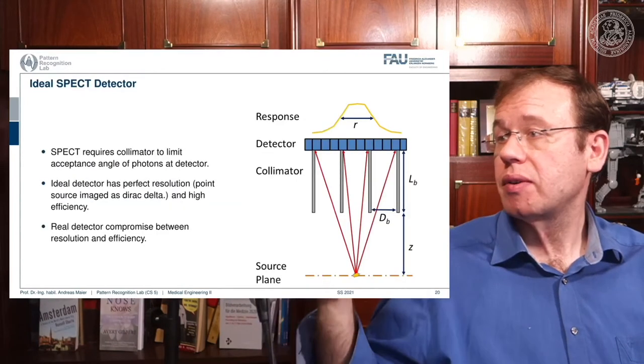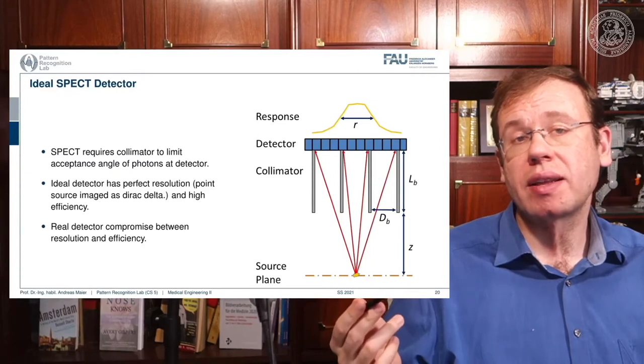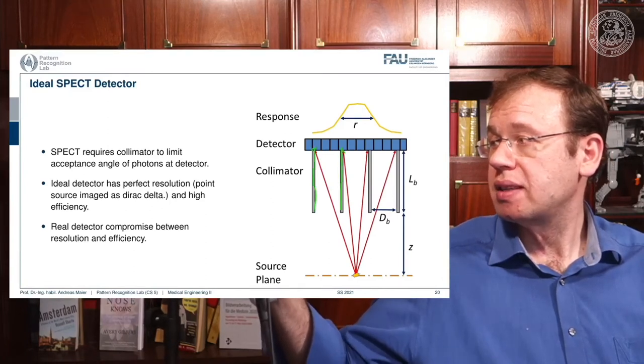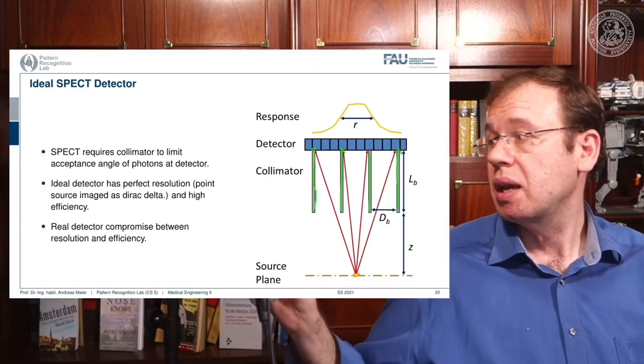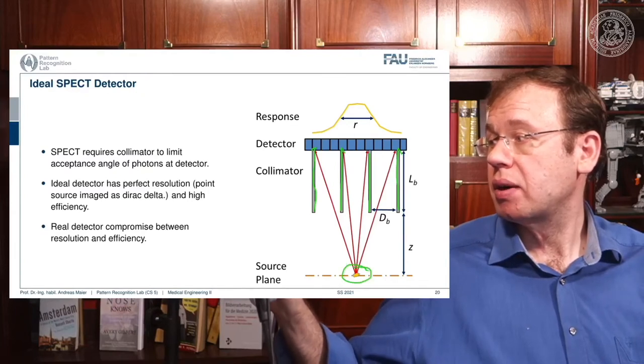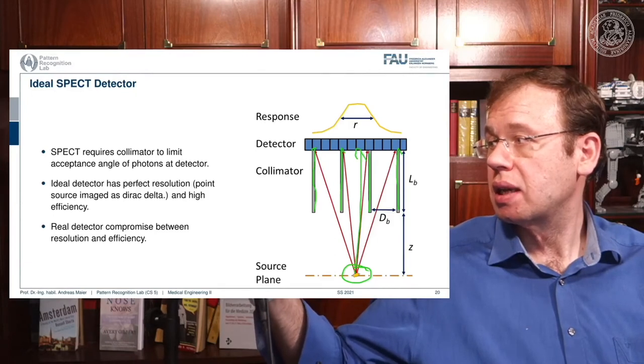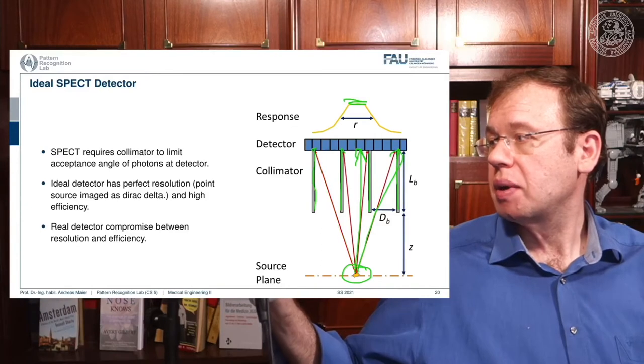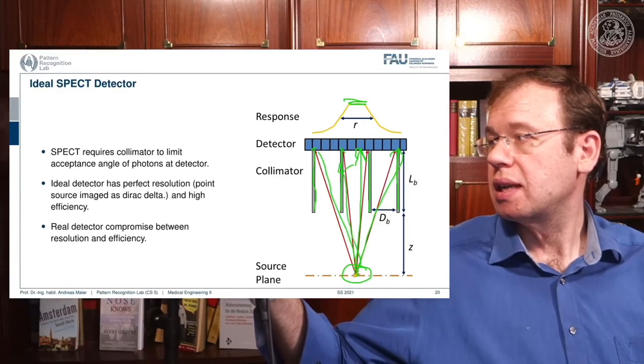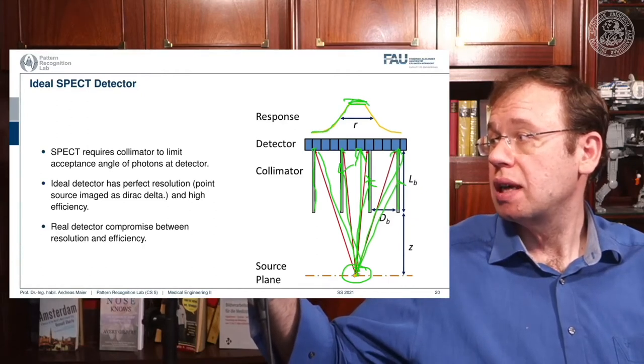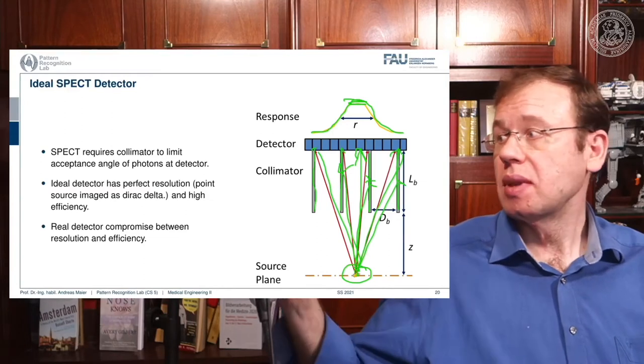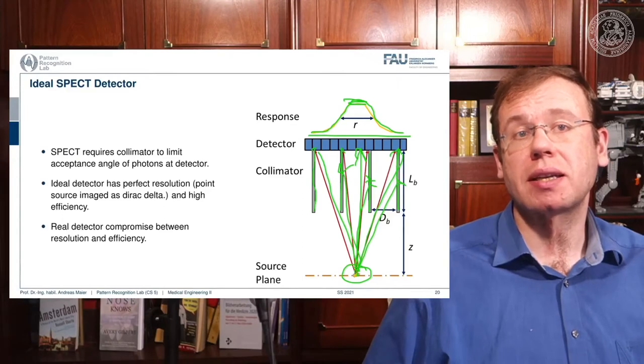A major challenge for SPECT is that we don't know where each gamma quantum originates. We use a collimator, similar in concept to the anti-scatter grid in x-rays. Events from a specific location pass directly through the collimator holes, giving a high response. Radiation arriving from other directions is blocked by the collimator, which absorbs those photons. This results in a sharper point spread function than without a collimator, enabling better image formation — particularly for SPECT.